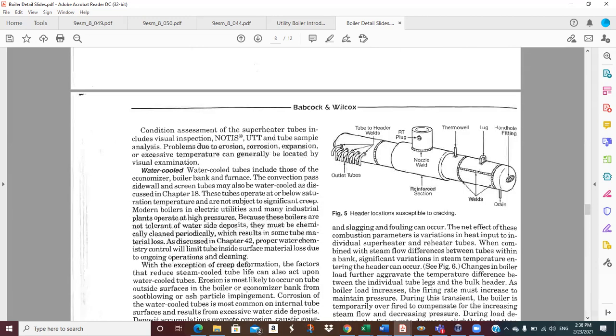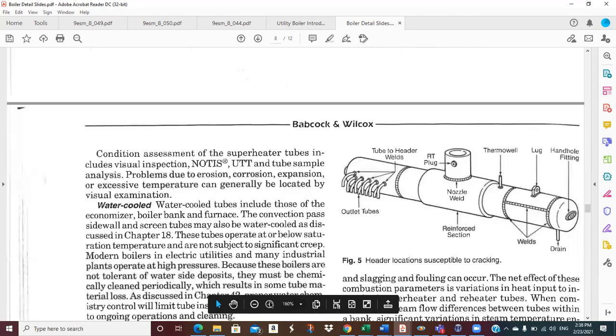Okay, this is to describe for you what a header is. The idea of a header is to take a single flow. We could assume that we had a steam flow, or it could be a water flow coming in here. And then basically we cut all kinds of holes all across this thing, and we stub and weld all these individual tubes. So if the water or steam's coming in, we're wanting to take that large flow from a single pipe and spread it into flow through all of these pipes. Like down at the bottom of the boiler, we're wanting to feed all of those water wall tubes with water from the drum. Well, how do we do that?